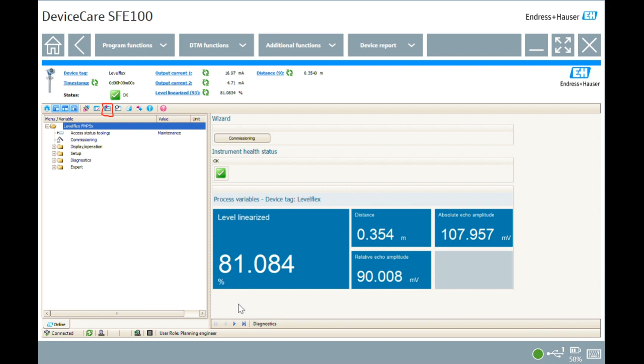The next button to the right is the record echo curves button. We'll click on that, and it opens up a new tab. Right below it, in that little red circle, that's our record curve button. Hit that and device care will pull a fresh curve from the device so we can start looking at it. Once that loads up, you'll see the curves in the middle.